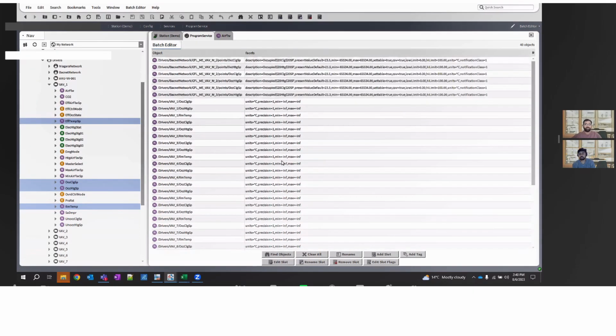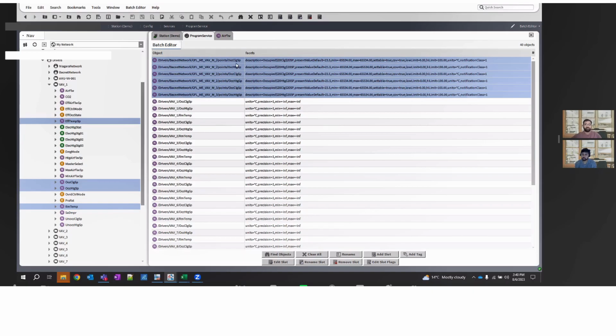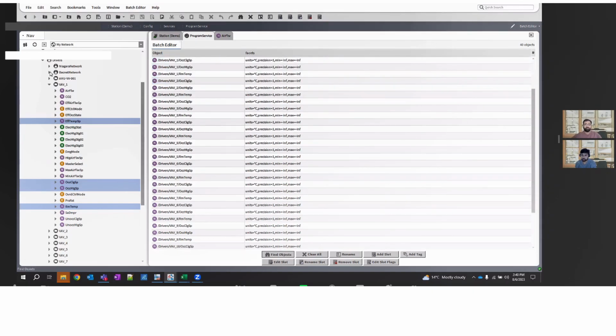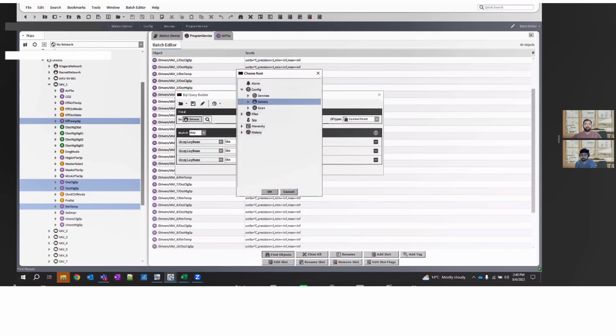And if you've noticed, it has even discovered the points of the occupied cooling set point from the VAV which we created at the start of the session in the BACnet network, because our scope was defined at the drivers level instead of any particular VAV or config level.